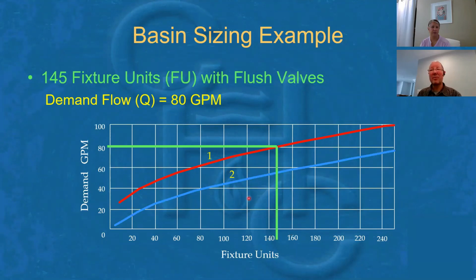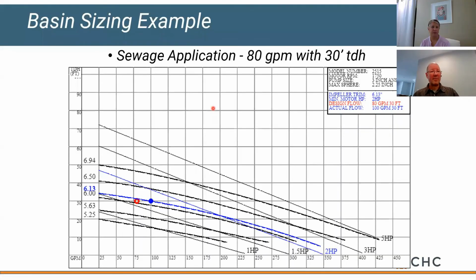Let's assume I've got 145 fixture units and I go to Hunter's curve and I establish that I've got a flow in my system of 80 gallons a minute. So that's how I'm going to pick my pump. I need 80 gallons a minute of flow. Sewage application, I've got 30 feet of lift, magically. So I'm going to pick a pump for 80 gallons a minute at 30 feet of head or lift. In this case, I've got a 2515. That doesn't mean much to you, but it'll pass 2¼ inch solids. That's fine for sewage. It's giving me a 2-horse motor. All this is good information.